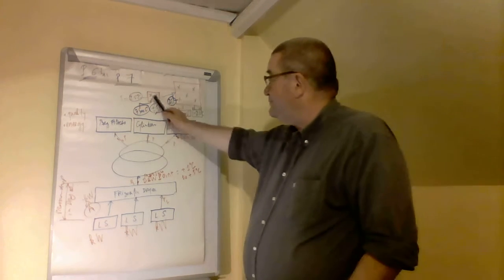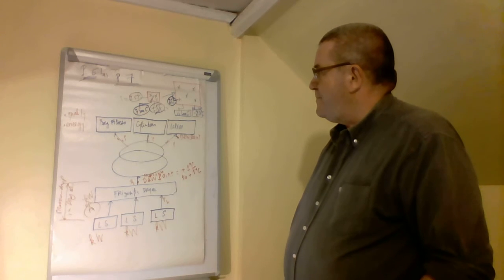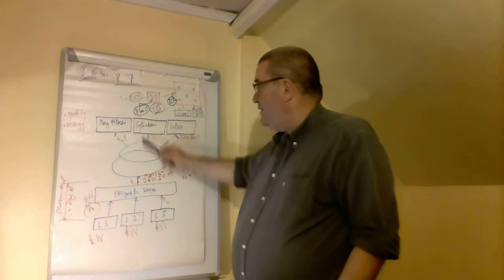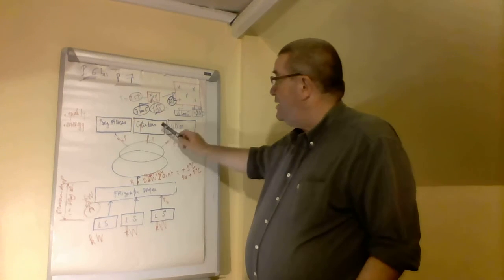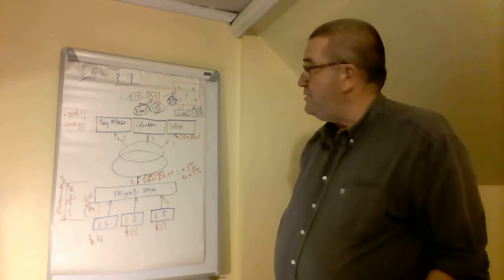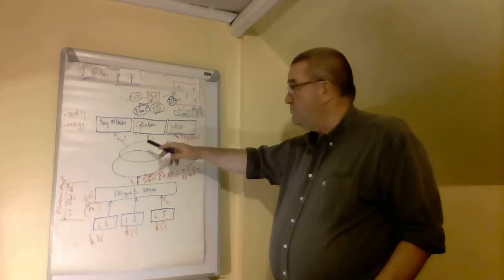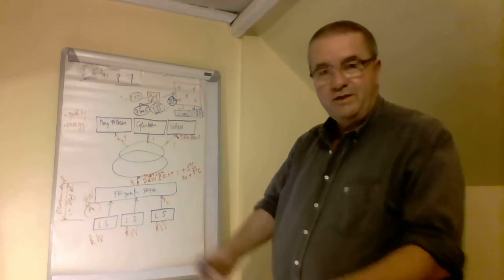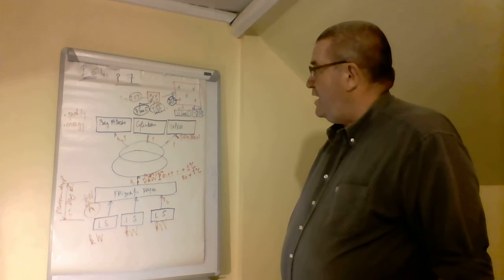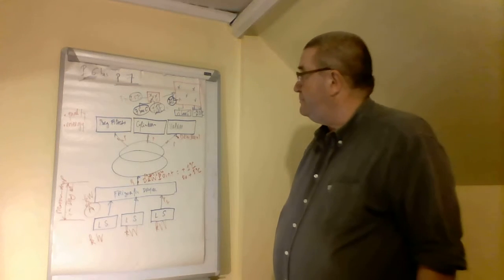Here you see that you may have problems if your pipe goes somewhere in the pipework in a place where the ambient temperature becomes inferior to +1 Celsius. If you are in a place where outside it is -10, which happens, then you will have some deposit of ice in your pipe.